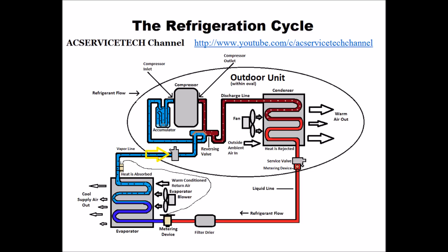It then continues through to the service valve, and at the service valve is where we typically measure total superheat. Right in the middle of the evaporator coil where the saturated state is, right after it comes out as a complete vapor, the temperature increase from there all the way to the service valve is called the total superheat — we typically measure that actual temperature within a few inches of the service valve. It then continues as low pressure, low temperature vapor refrigerant through the reversing valve and into the accumulator, whose job is to make sure the compressor does not receive any liquid.